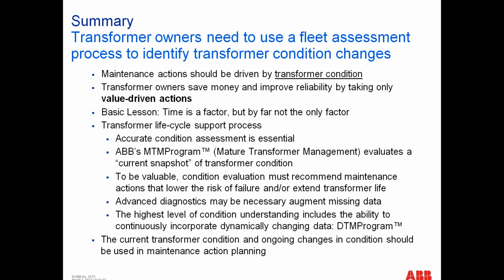If you're in the desert of Arizona or southern Florida, you lose a lot of life from your transformers in summer when customers run heavy air conditioning loads. In a more northern climate, life may be a little better. And if you're lucky enough to be in Canada, which often has peak load in winter, that's actually the friendliest environment, since you're hammering the transformer hard, but at a low ambient temperature. So time is a factor, but not the only one.